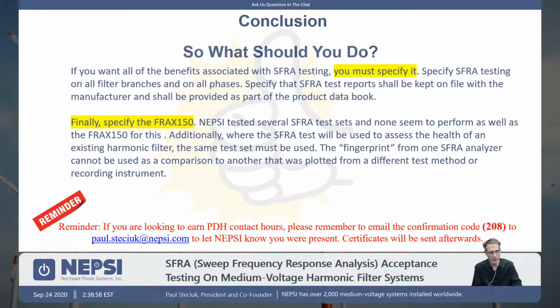And remember, you want to ask for a test report, you want to ask for the digital file. And if for some reason in the future you have some type of issue with that filter system, you want to make sure that you use the same SFRA test set. It's got to be the same one, Frax 150. That way you can overlay the plots and you can determine if the system was damaged or not.